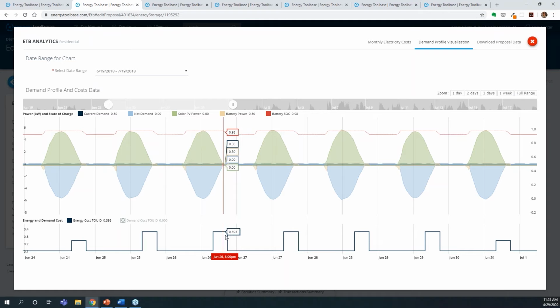And the reason why is because there's a really wide price differential between the on-peak and the off-peak period year-round. Literally 365 days of the year, there's a viable opportunity. And you can see here on this particular day in June, the on-peak rate for the TOUD prime, which by the way is 4 p.m. to 9 p.m., is 39 cents a kilowatt hour. Off-peak rate, about 13.5 cents a kilowatt hour. So call it maybe about a 25, 26 cent differential.